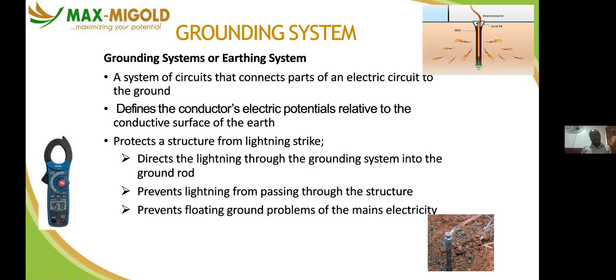So that's why you use copper. Copper has high conductivity. And you use an electrolyte, like the salt that you pour in your earth pit, to enhance the conductivity of any leakage current to the ground. An electrolyte is anything that allows the passage of electricity in liquids or aqueous solution. So that salt helps to conduct the leakage current from your installation to the earth without any disturbance. So that's why you cannot compromise your earthing system. Ensure that the right things are used in your earthing.